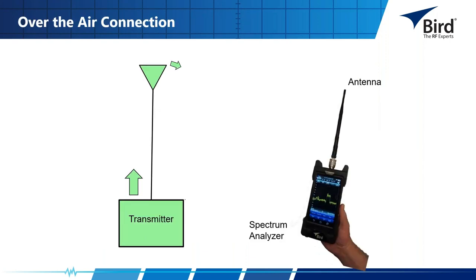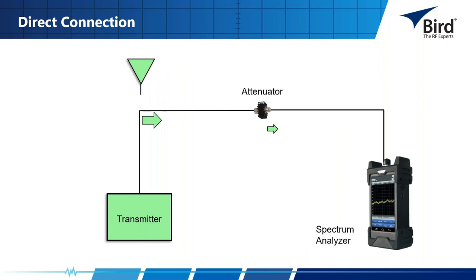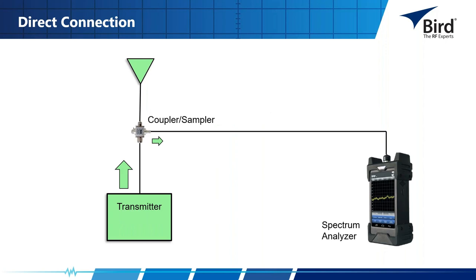For an over-the-air connection, the transmitter puts out a signal that goes up to its antenna, leaves there, and arrives at the antenna on the test port input of the spectrum analyzer. For a direct connection, if your signal is above +20 dBm out of the transmitter, you want to put an attenuator on it to limit power going into the analyzer. You can also connect directly to an antenna through a sampler or coupler, with the coupled signal going into the spectrum analyzer.